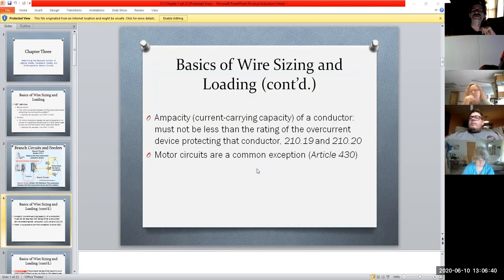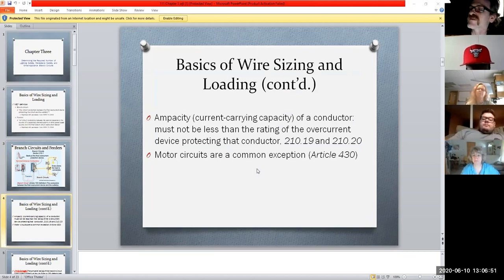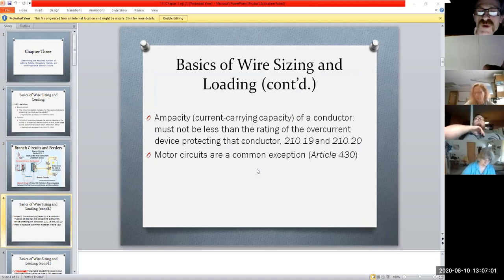Hopefully that makes sense. And again, I always go back to ampacity, ampacity, ampacity. It's our ability to deliver. It doesn't mean we're always going to deliver 20 amps, otherwise your meter is going to be going crazy. We're not always going to feed 15 amps or 30 amps or whatever size the breaker is, but we have the ability to deliver that if needed. So my limiting factor here is very typically the overcurrent device protecting that conductor, which is the circuit breaker or the fuse in this case.